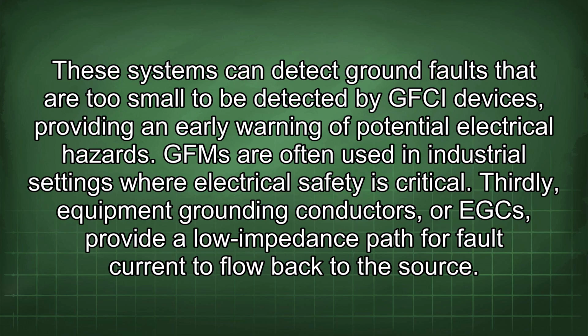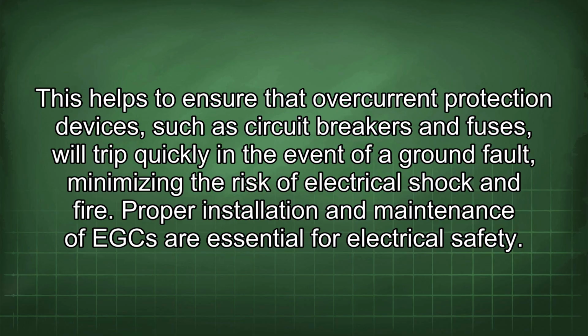Thirdly, equipment grounding conductors, or EGCs, provide a low impedance path for fault current to flow back to the source. This helps to ensure that overcurrent protection devices, such as circuit breakers and fuses, will trip quickly in the event of a ground fault, minimizing the risk of electrical shock and fire. Proper installation and maintenance of EGCs are essential for electrical safety.